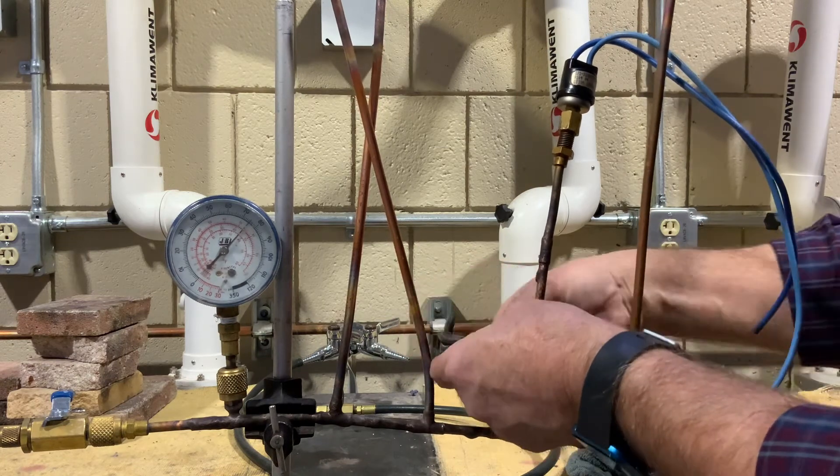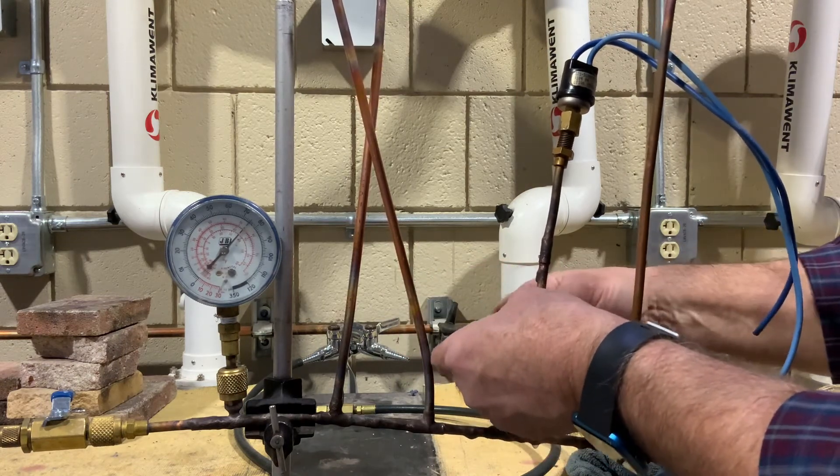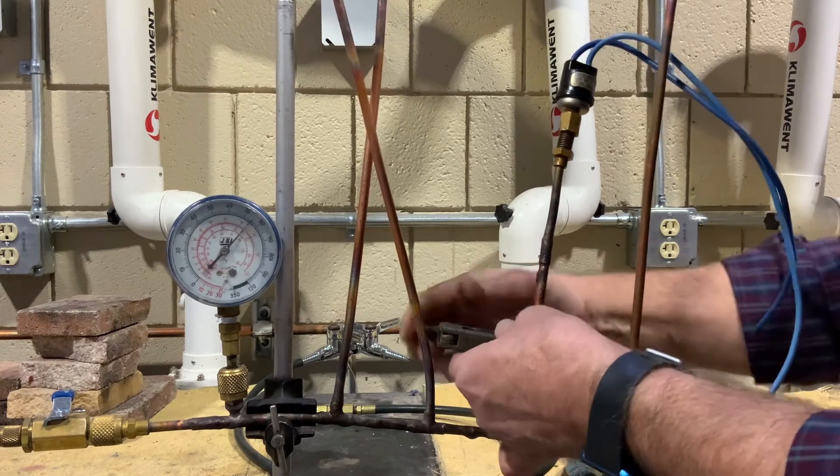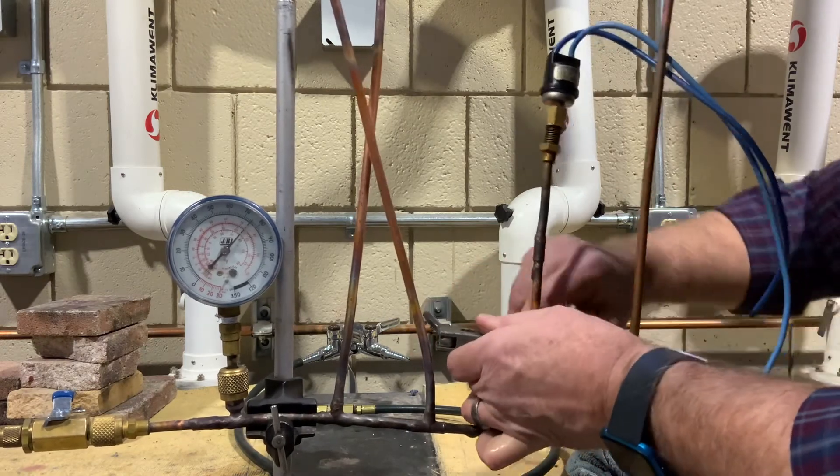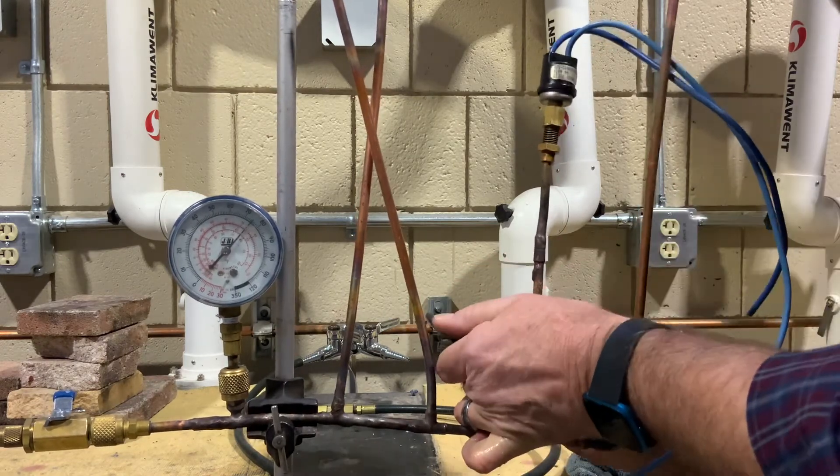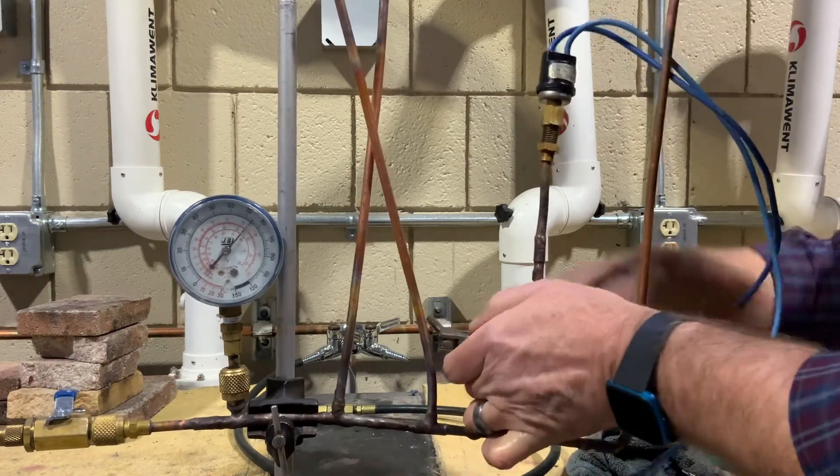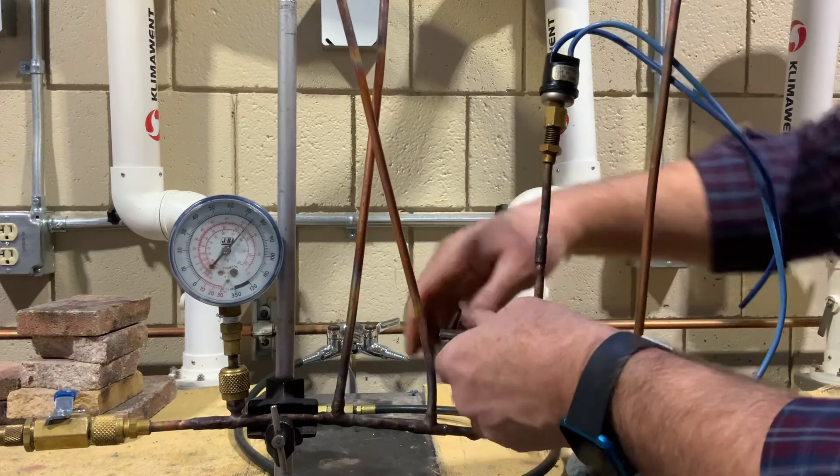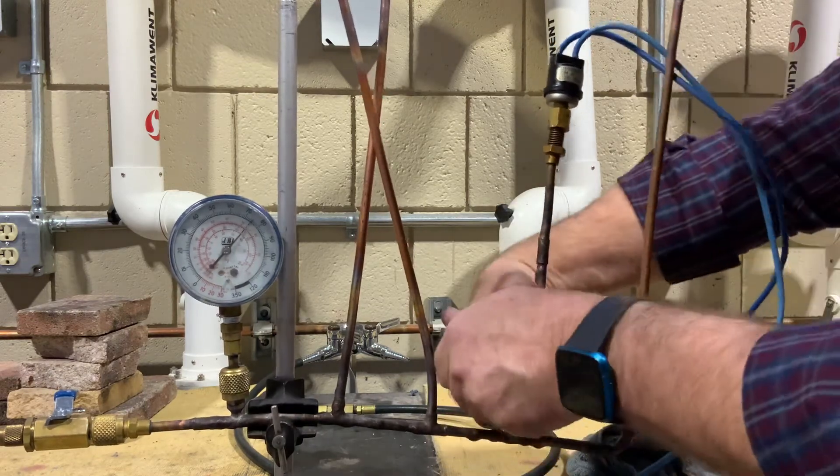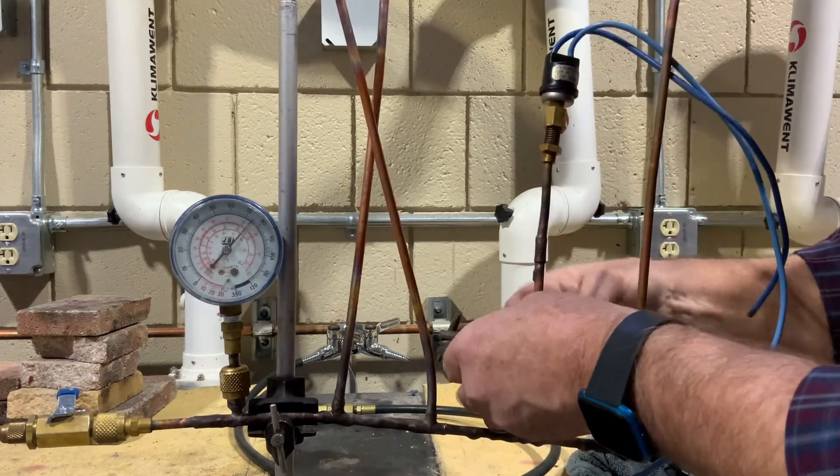We don't need to make it perfect. Pressure's pressure. We just got to get pressure through there so that pressure switch can read pressure. So we're just going to put that the opposite way of our pinch. We're going to tighten that down. And open that hole back up.